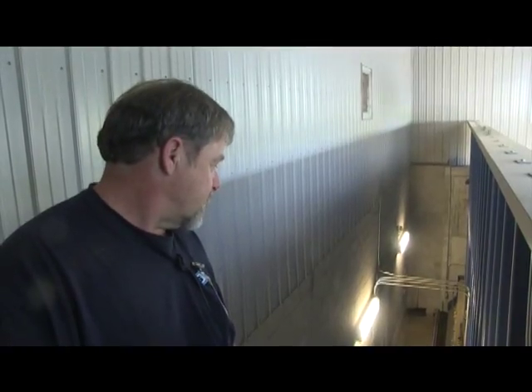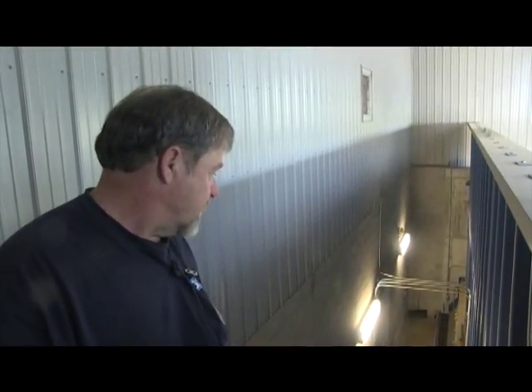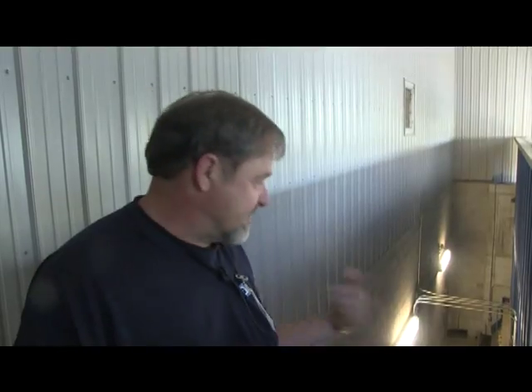And so what happens is the system is all automated. There's an electronic eye on a metering bin out in the boiler room. When that laser sees wood, it says, it's time to bring me wood. So the system starts up, it automatically pulls wood out onto the belt. The belt fills the bin. When the sensor stops seeing wood, it says, stop the belt, stop the wood delivery. So that's really a really basic, really simple system.